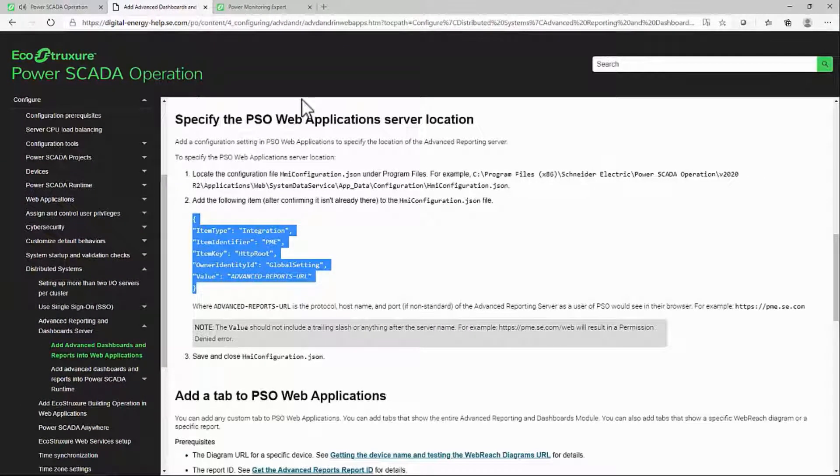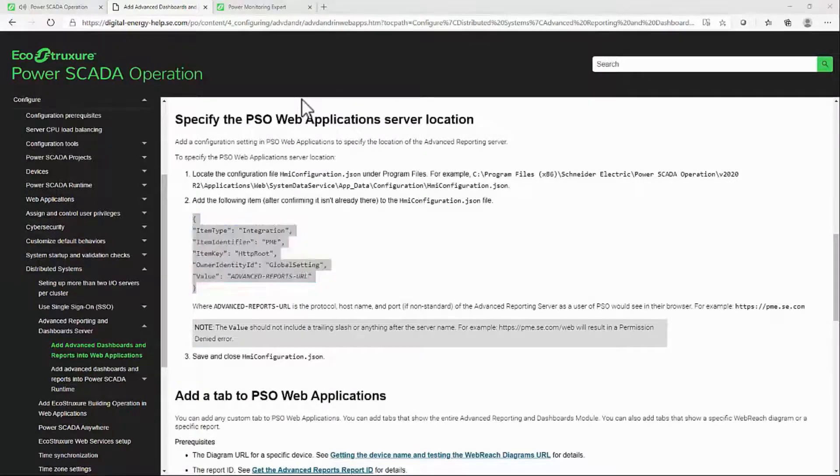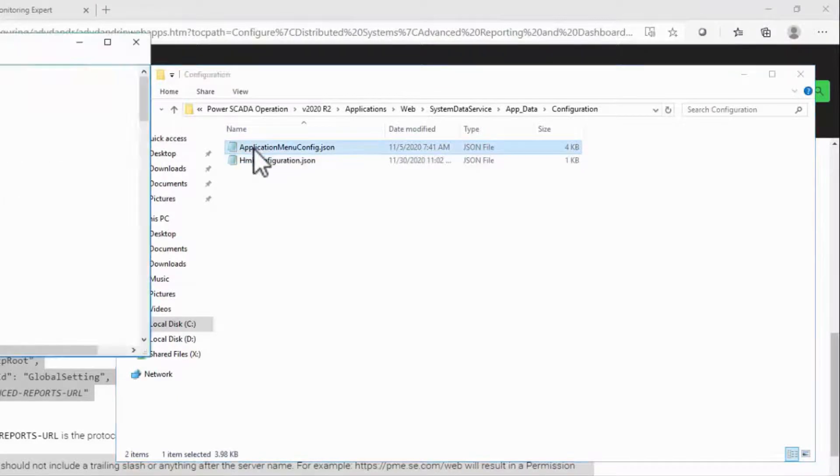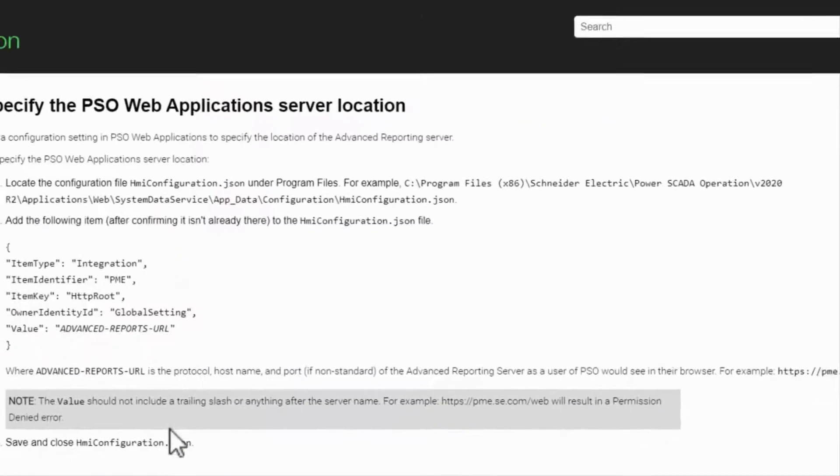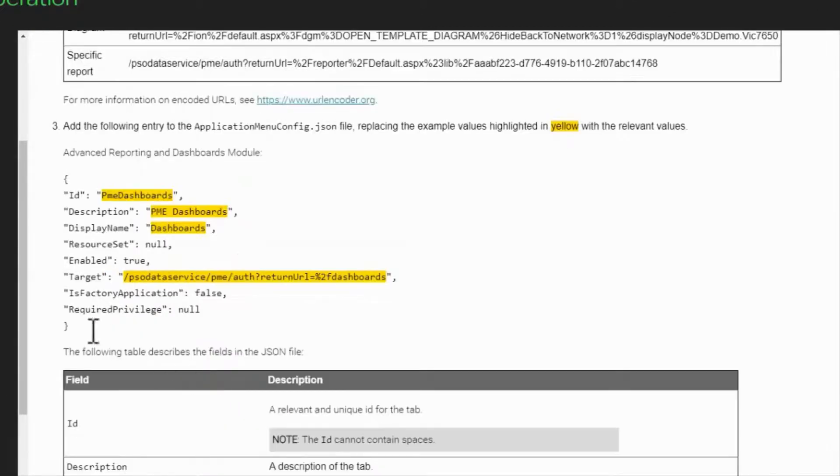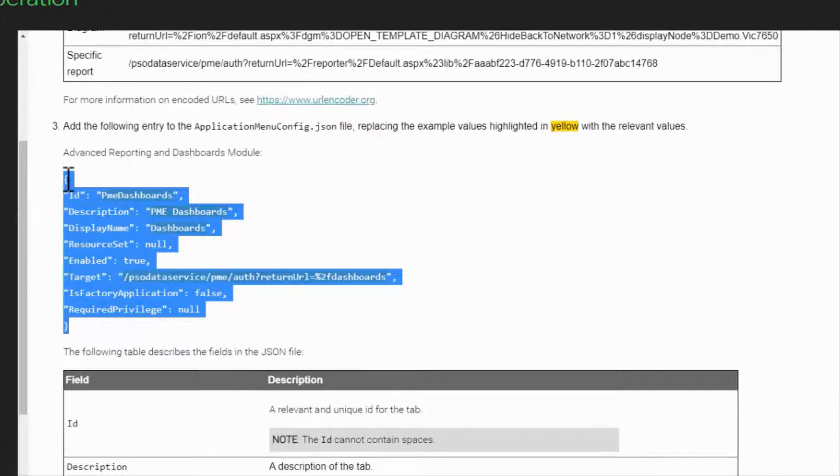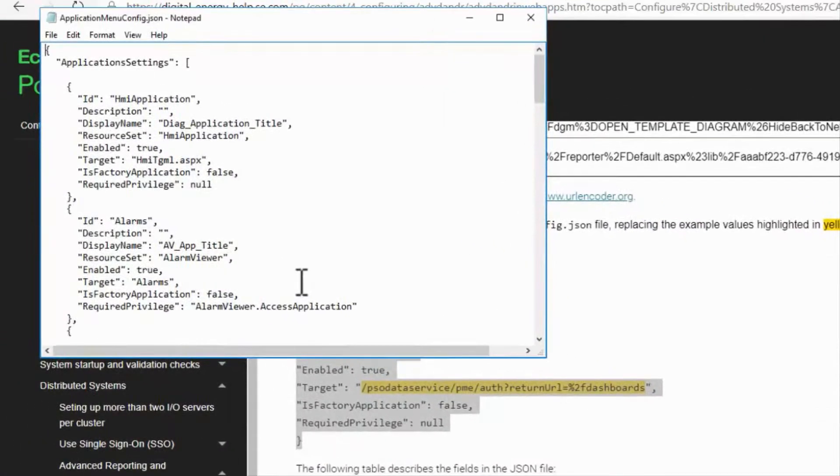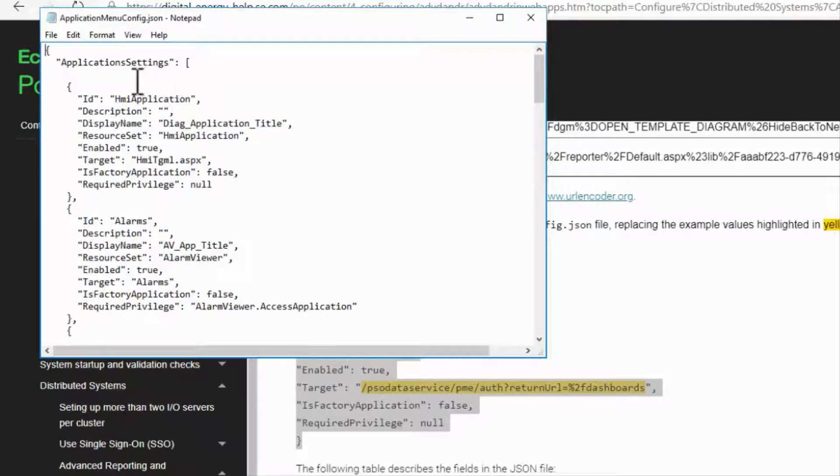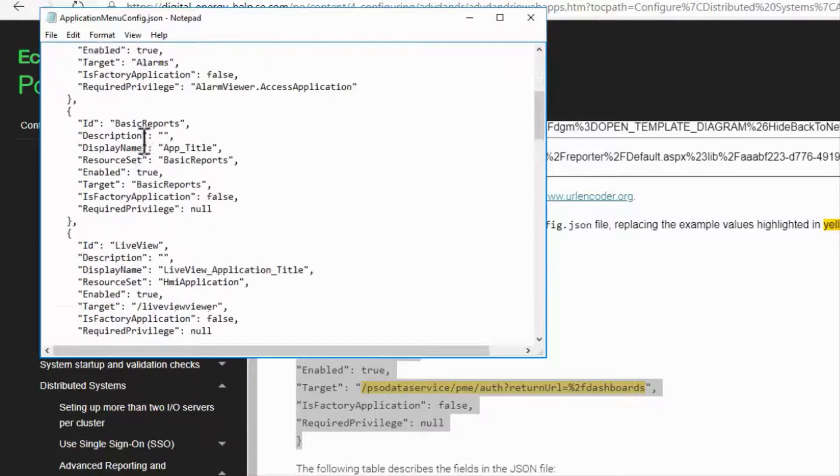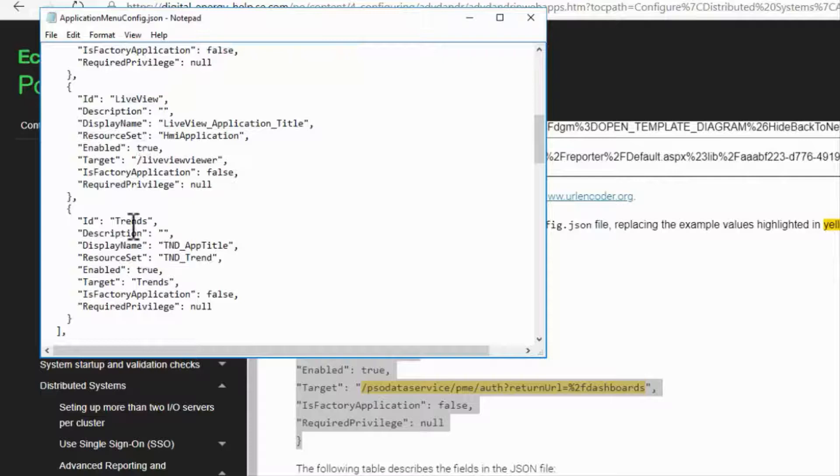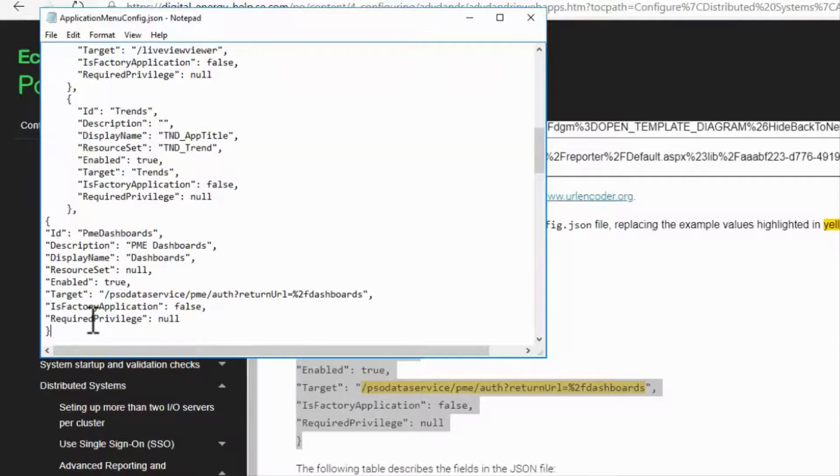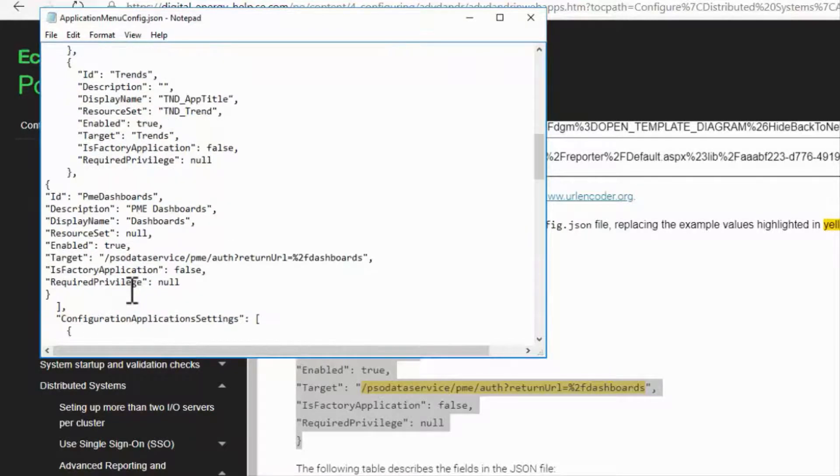Next, we'll add the Reports tab to the WebHMI in the file ApplicationMenuConfig.json. As before, copy the second JSON block out of the System Guide. We need to paste this in a specific location inside this file. The first array here is called Application Settings, and this contains our menu in order. At the end, I can see the Trends button, so let me add a comma and paste in my new menu entry. Be sure not to scroll down and paste in one of the other objects.